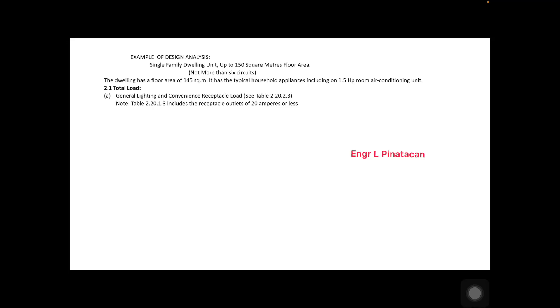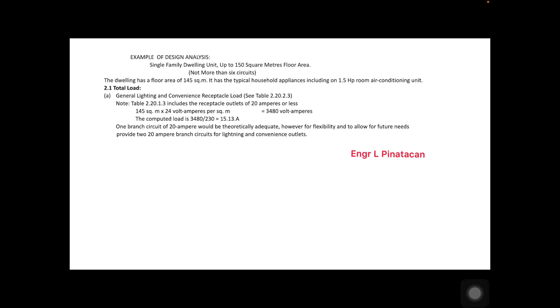For the general lighting and convenience receptacle load, we check table 2.20.2.3 in PEC 2017, and table 2.20.1.3 which includes receptacle outlets of 20 amperes or less. For 145 square meters, we multiply by 24 volt-amperes per square meter. The result is 3,480 volt-amperes. The computed load is 3,480 ÷ 230 volts = 15.13 amperes. One branch circuit of 20 amperes would theoretically be adequate.